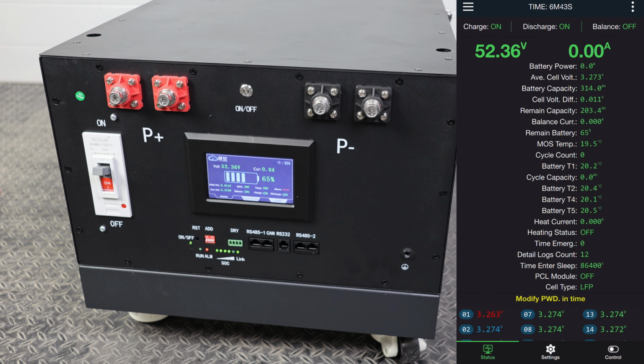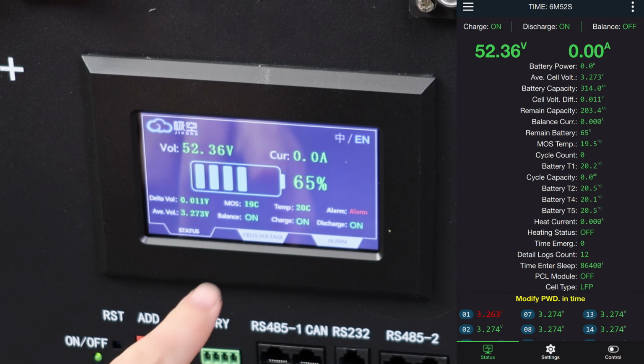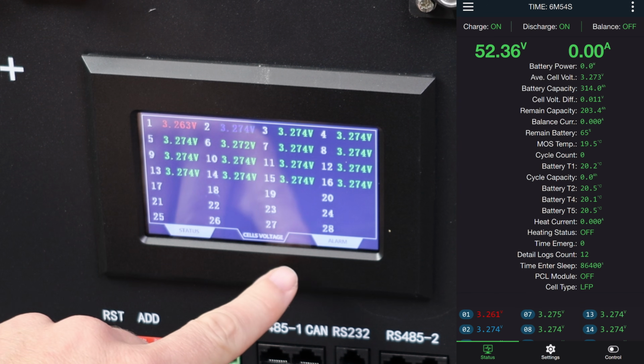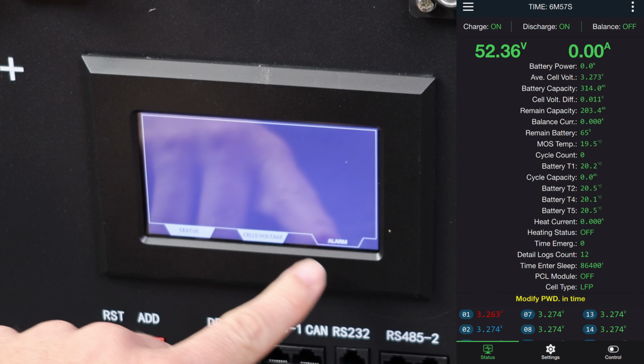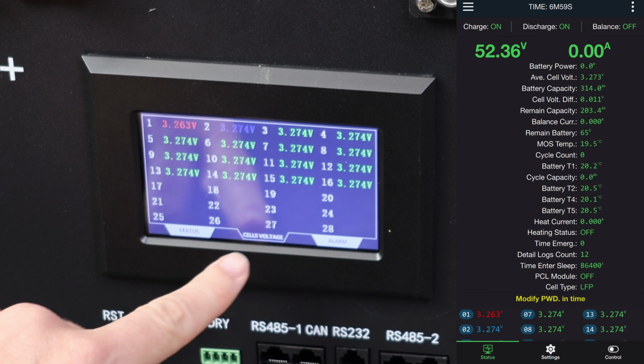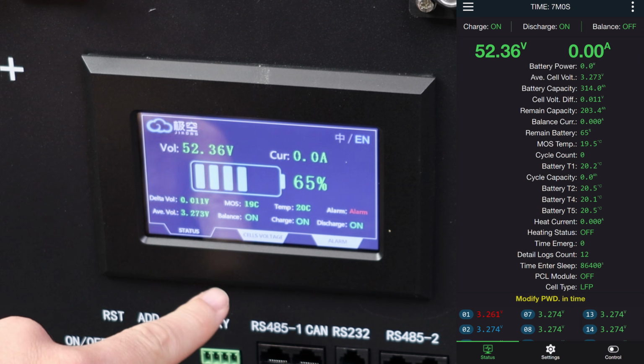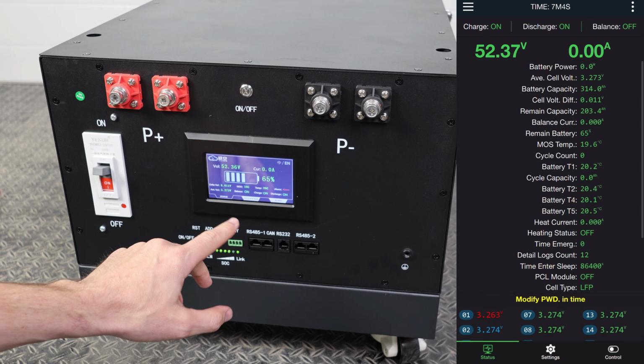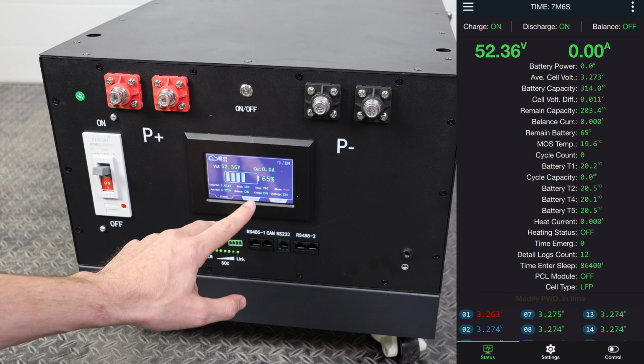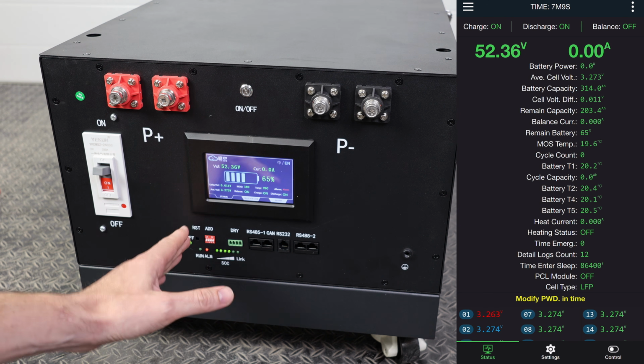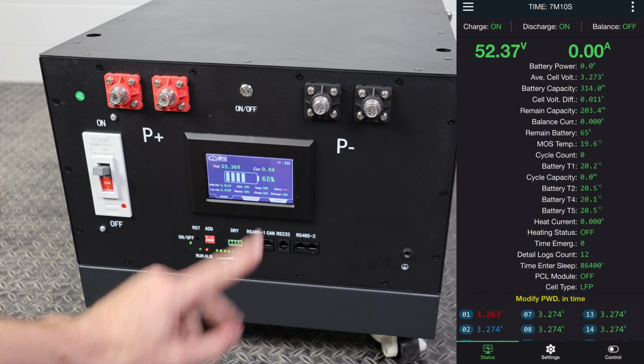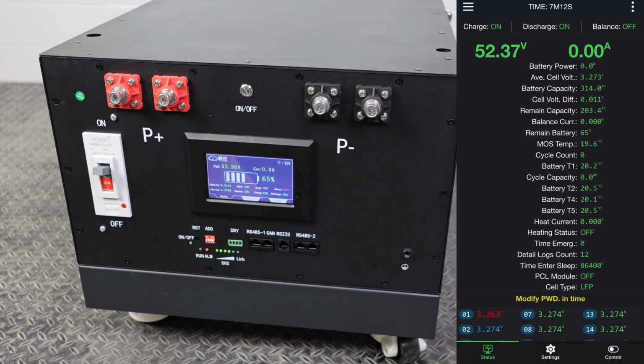It started up and that was easy—we just selected the setting, adjusted a couple of values, and we're good to go. We also have access on the screen where we can see any alarms, the cell voltage, and the status of the overall battery, which is really handy. It's showing 65% right now, which is probably not too far off, but we're going to charge it to 100%, make sure everything's balanced, run a capacity test, and then do some testing with it.